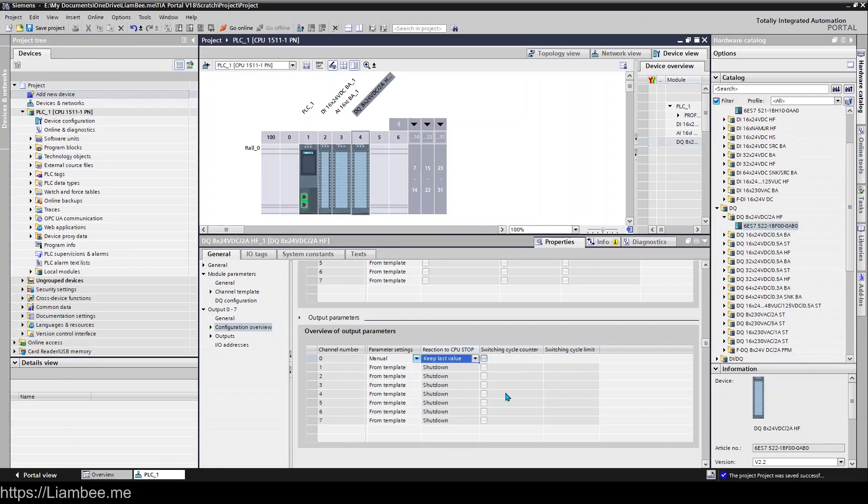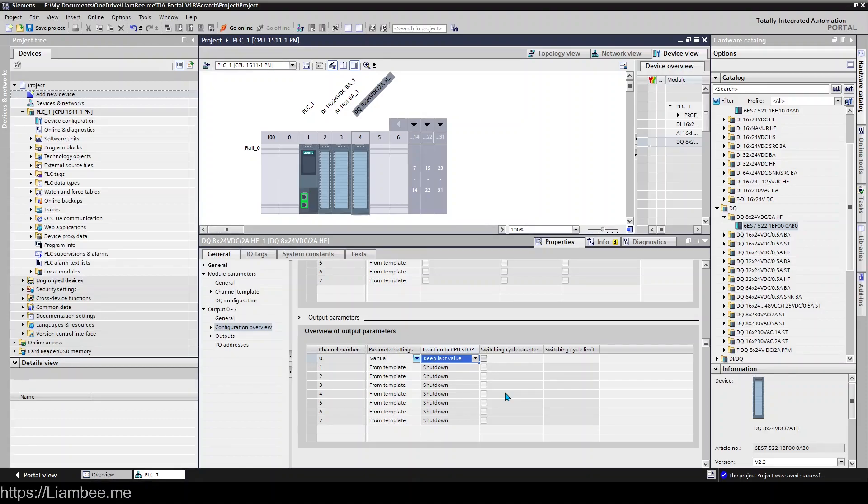And knowing that that information is there or that parameter setting is there can be useful for situations where you're working with something that you can't just de-energize because of where it is in the program. You need to make sure that you keep the last value if you can because it's safer to do that.